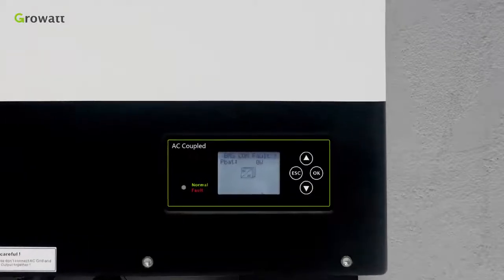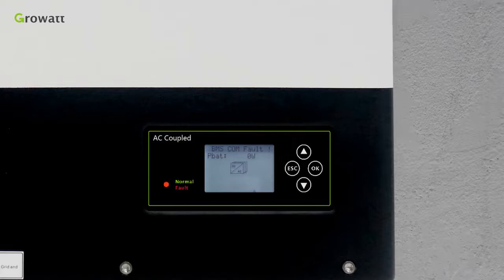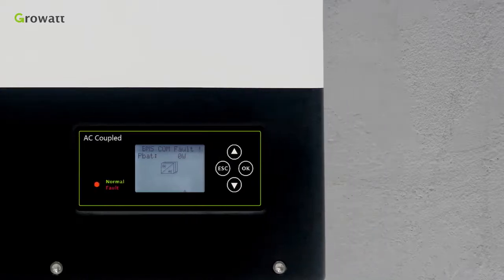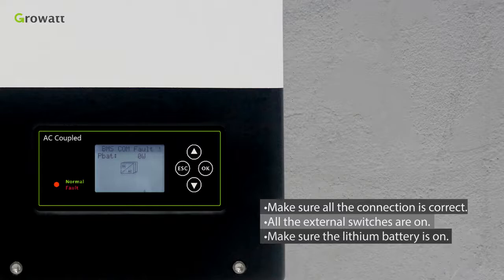If SPA do not enter normal mode successfully, especially if the LED is red, you need to check below. Make sure all the connection is correct. All the external switches are ON. Make sure the lithium battery is ON.